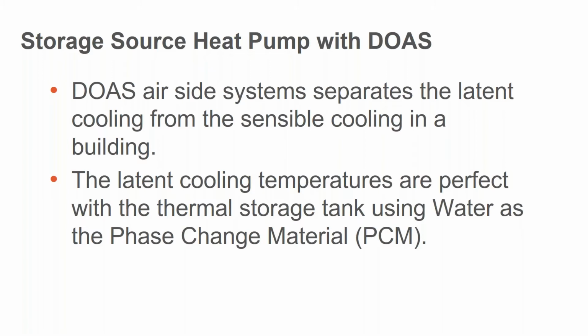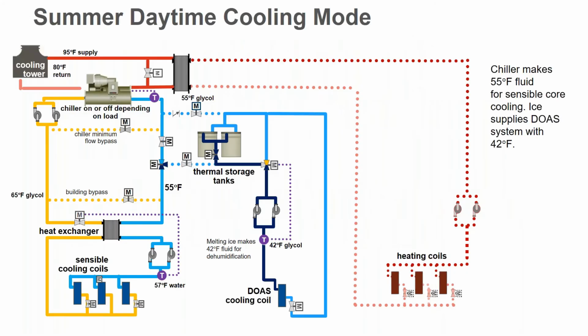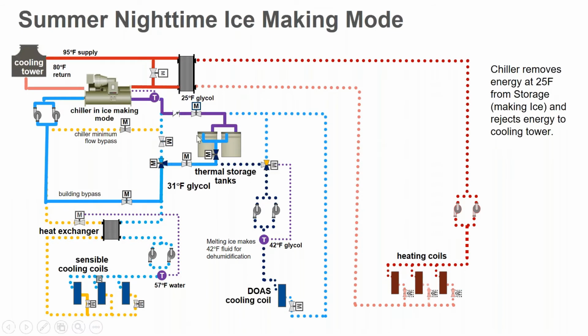It turns out that 32 degrees is just about a perfect temperature for a phase change for storing energy when you are running a system in this fashion. So all I've done is broken the cooling coils into two here. We have the sensible cooling coils down here, which are being supplied a much warmer temperature liquid. So we'll call this the high temperature cooling coil. You want to supply it with a temperature that's not going to cause any condensation, so that certainly has to be looked at. But it's clearly a much higher temperature for the chillers to operate at, and at very, very high efficiency.